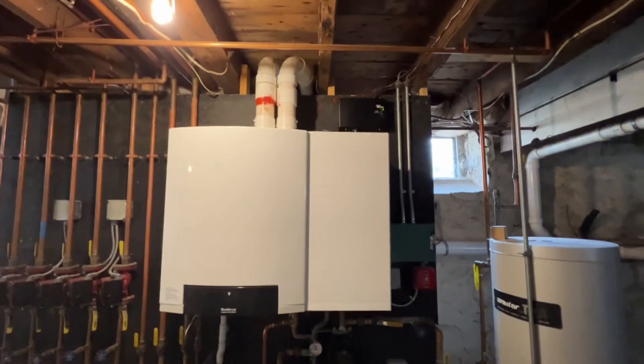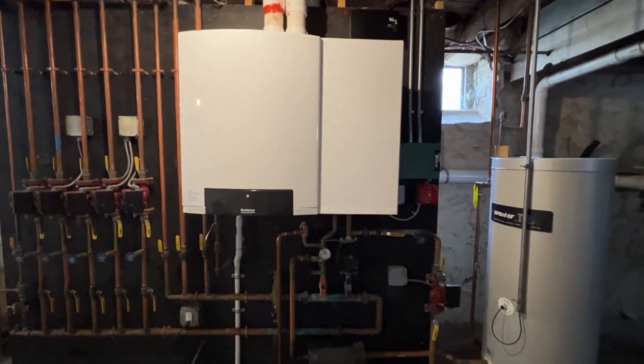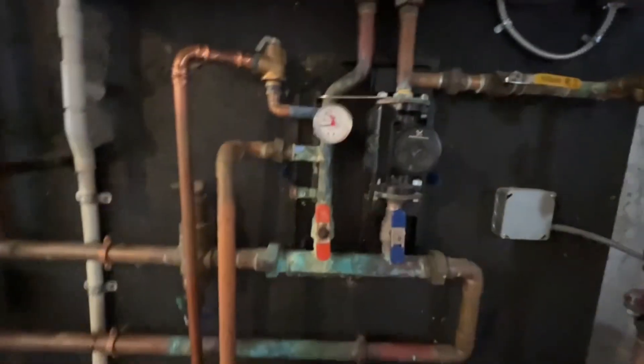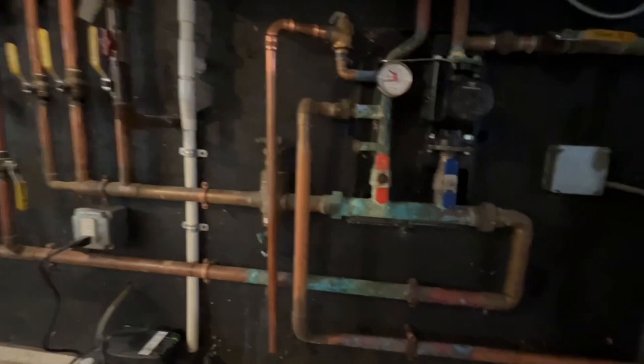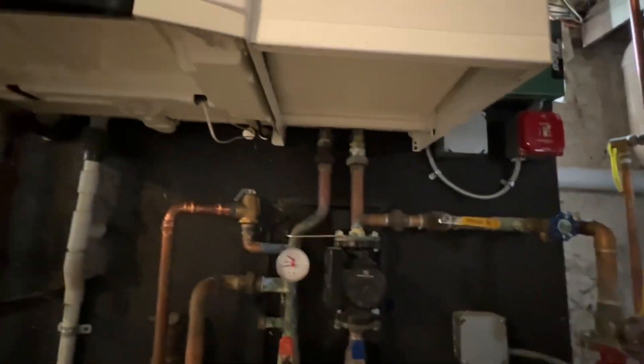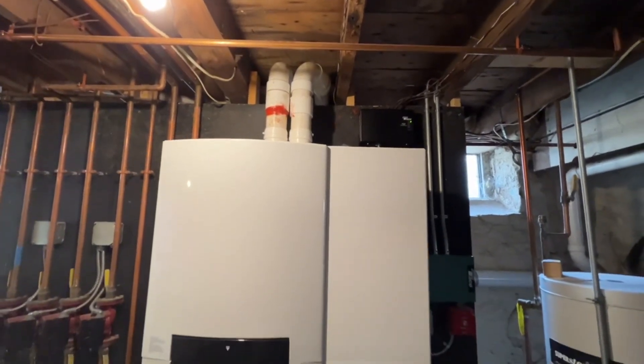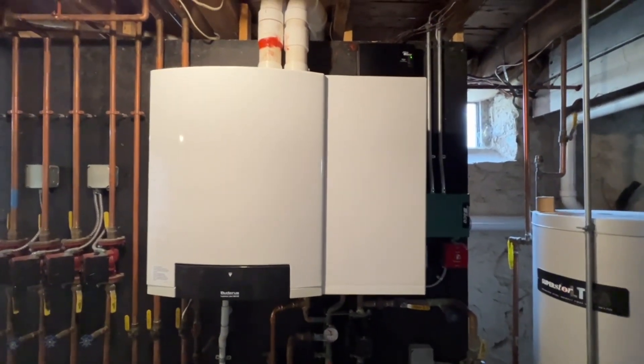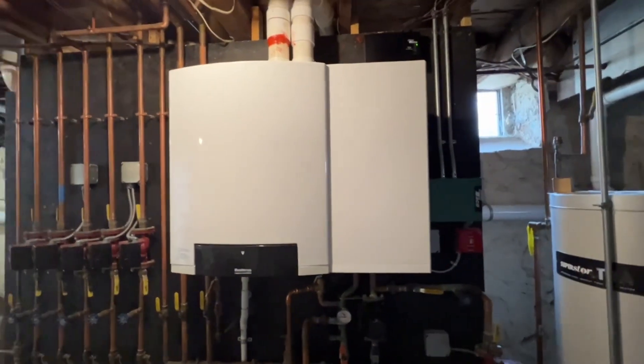Today we're at Debacle Plumbing and we're going to be removing this early 2000s model cast aluminum boiler from Buderus that has rotted out. We're going to try to leave the supply and return manifold and put a new primary secondary heat loop here. I'm going to reuse this Superstor Ultra indirect. This is the piece that failed, so this is what we're going to work on getting out. We're putting in a new Lochinvar, made in USA, high-efficiency stainless steel wall-hung boiler with a 95% efficiency rating.